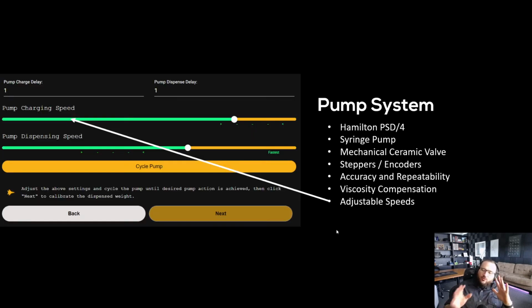And finally, one of the really cool things about our pump is the ability to change the speed between the charging and dispensing stroke. So in other words, you can independently set the speed as the syringe pulls back or as it pushes forward. And that really comes in handy because our supply side is pressurized with nitrogen. So certain fluids that don't like to be exposed to vacuum or they start bubbling a lot inside the cartridges are able to be filled with our machine because you can just slow down the charging speed and wait for the fluid to be pushed into the syringe rather than allowing the syringe to pull a vacuum up inside. Now, if you're doing something like distillate with terpenes, doesn't matter, just go fast.